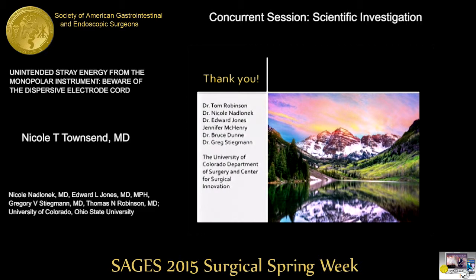We're all very much in the routine of bundling all of our cords as they come off of the operating room table, and so draping the active electrode cord on one side of the patient and everything else on the other side of the patient is sufficient to mitigate that effect. And we have not specifically looked at an addition of insulation, but I think that's a great idea and something that we could explore. Absolutely. Thank you.